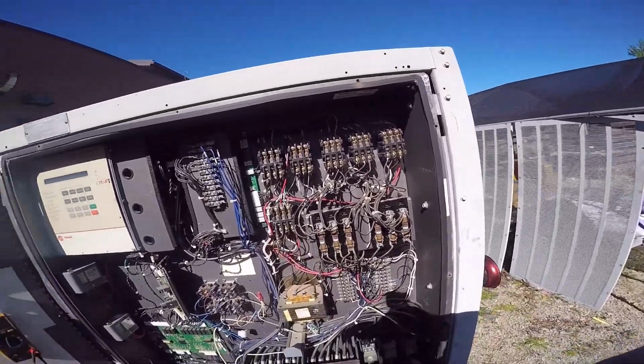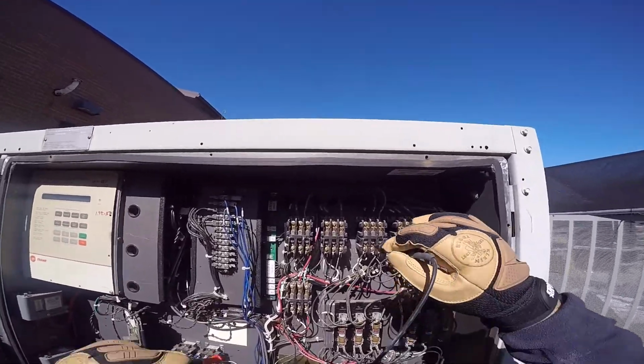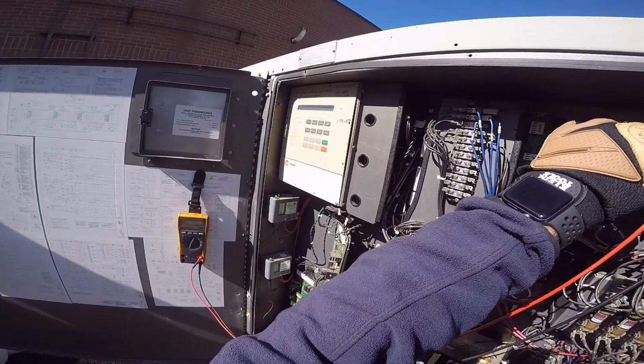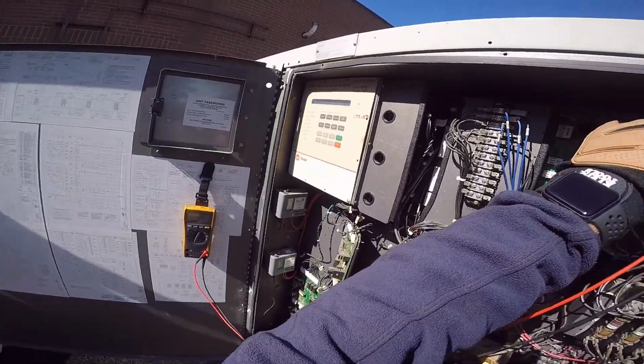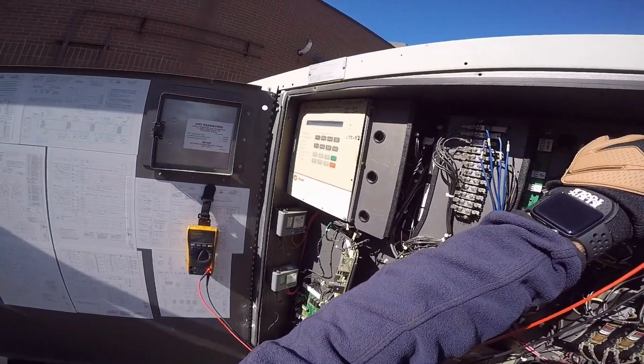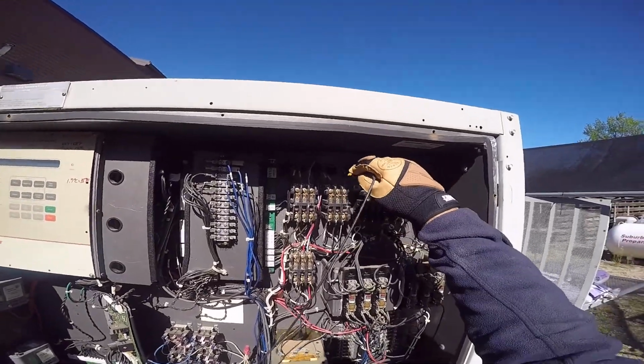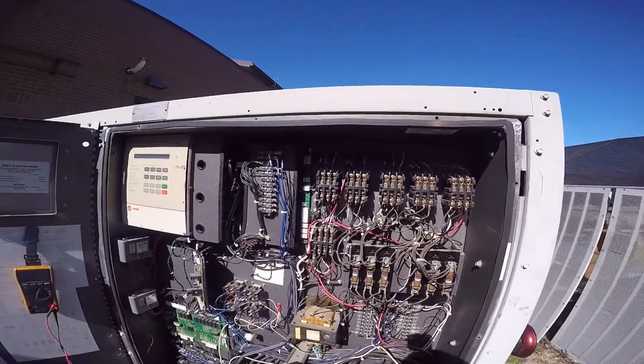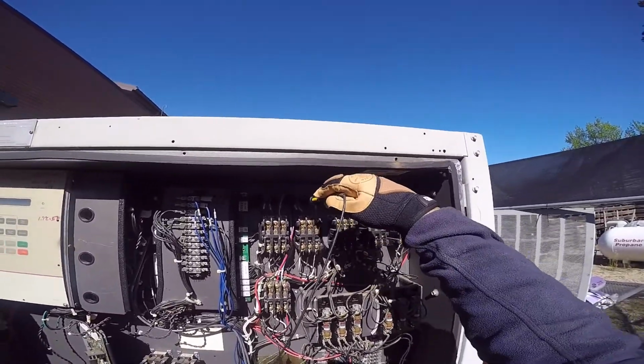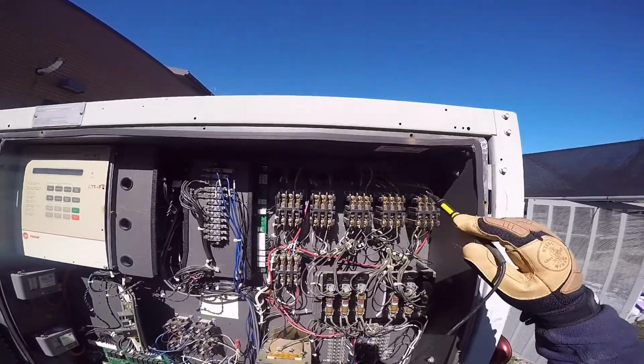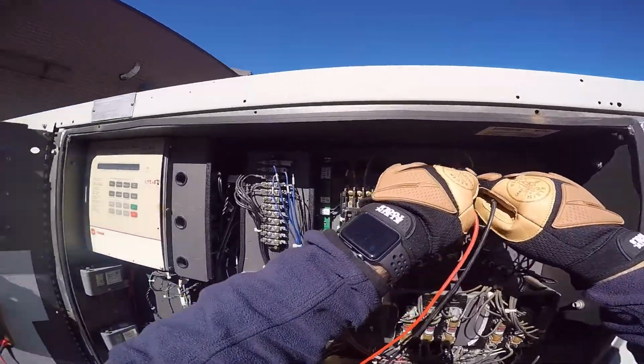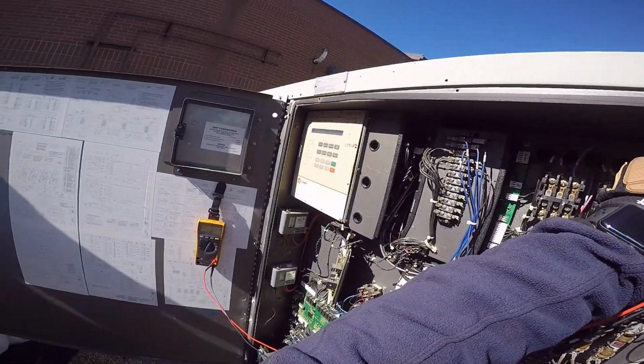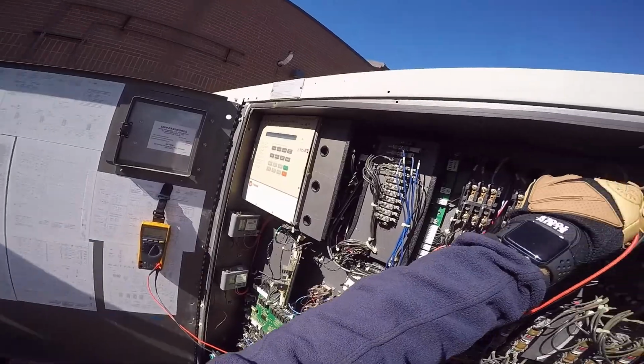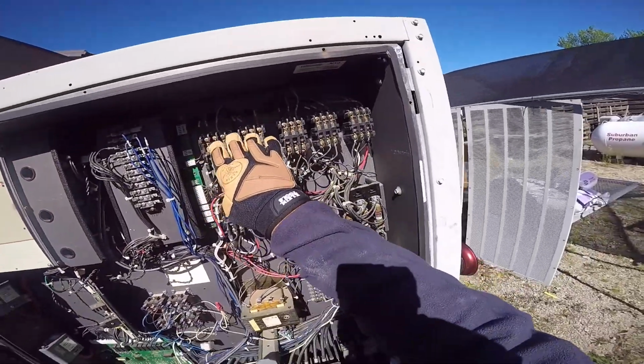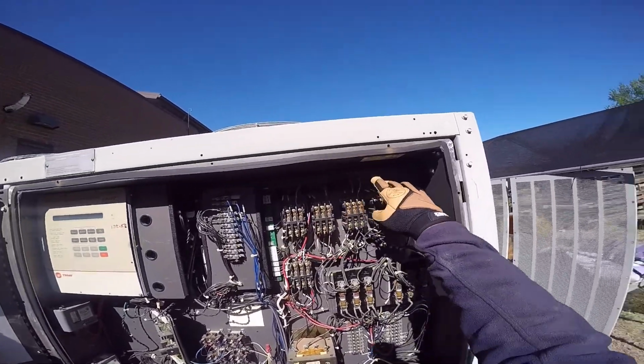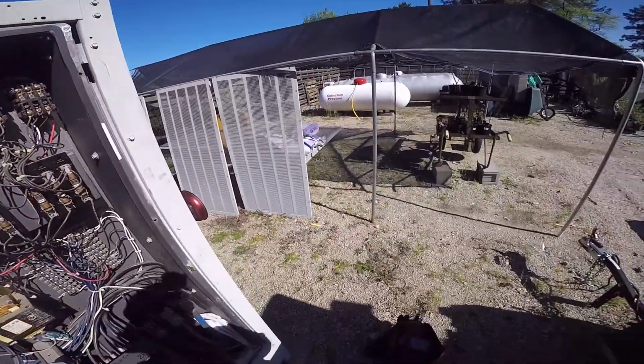You ohm these motors out. You could go to ground as well, but if it's to ground, your ohms through the legs are going to be different. And I don't care what the motor is. All I know is I want to see all 3 legs read the same ohms. Now, if there's anything else on this circuit besides these wires going straight to a fan, you'd have to disconnect stuff to get a clean reading. But these are one fan per contactor. The contactor is not pulled in, so I've got nothing interfering with my ohm reading. See, that's 5.1, that's 5.1, and that's 5.1. That's the same fan motor as these two. These two read 3 ohms. This one's reading 5 ohms, but all 3 legs read the same, so there's nothing wrong with that fan motor.